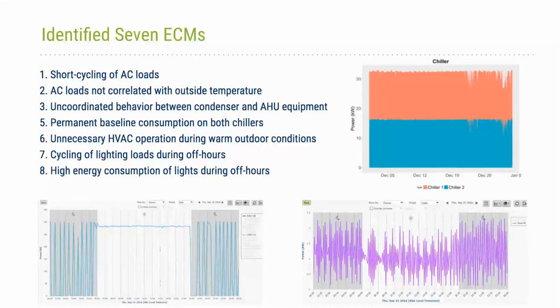They were also able to see unnecessary HVAC operation during warm outdoor conditions and cycling of lighting loads during off hours, as shown on the bottom left. This lighting system was actually turning on and off during the night, as well as showing high energy consumption of lights during off hours. All these ECMs they were able to identify, and they left that information for the building manager to act upon.